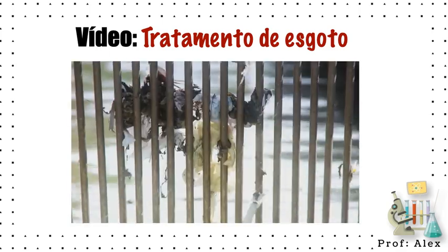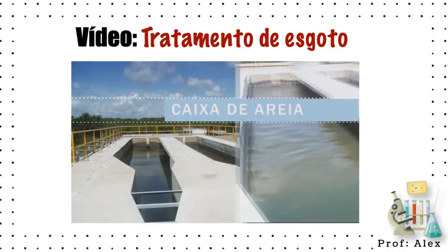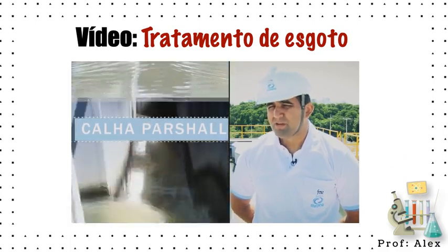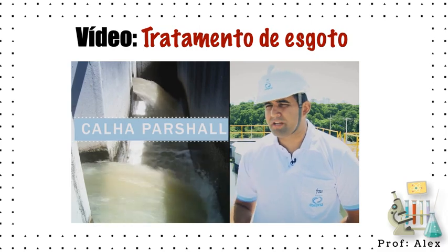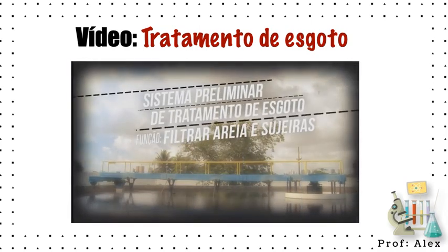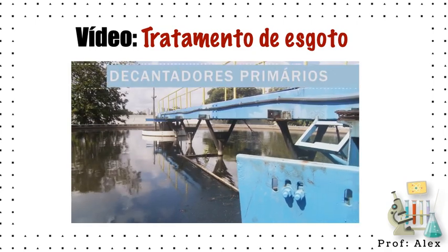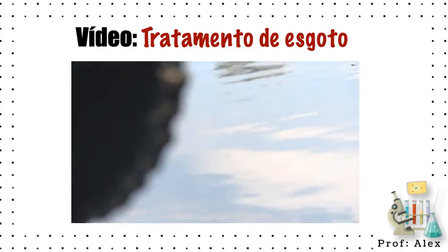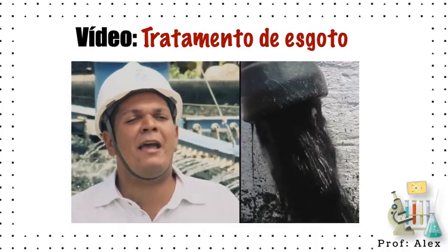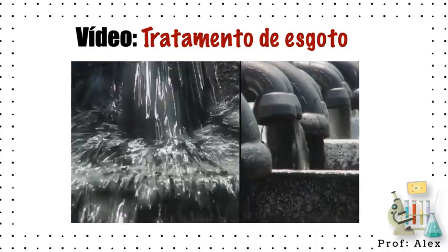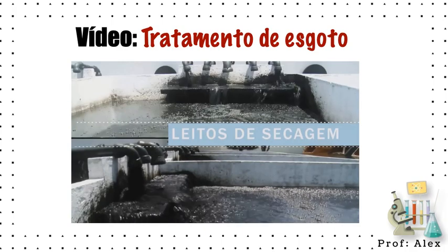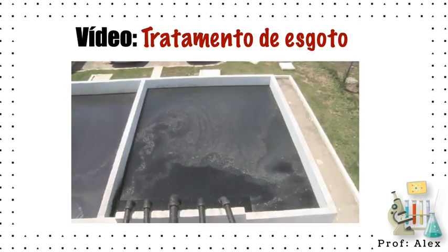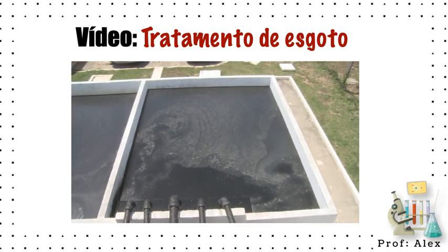The function of the screen is to retain the coarse waste before it reaches the downstream processes. The caixa de areia is a system for sand removal. It monitors the amount of sand entering the system. In the primary system, we have the primary decanters, which retain suspended material through a slow decantation process. This material is removed and sent to sludge treatment, which aims to reduce physical volume, remove humidity, and reduce pathogens such as viruses and bacteria.